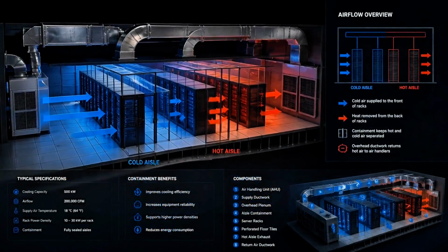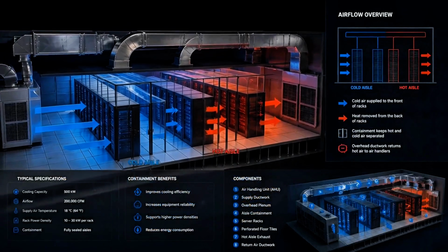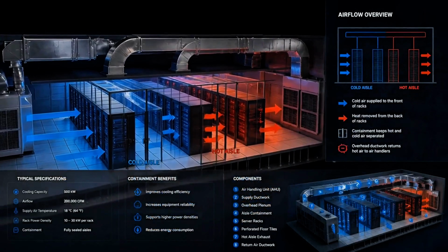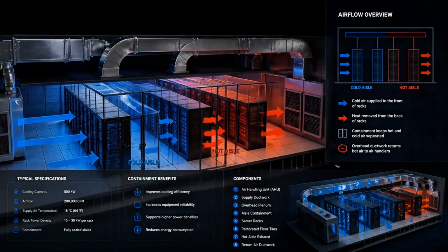Traditional data centers remove heat with air. Fans pull cool air through the front of each server. Warmer air exits at the rear, where containment systems separate hot aisles from cold ones. Air handlers then transfer that heat into the facility's cooling system.